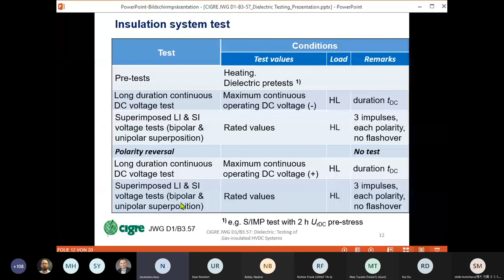calculated or can be evaluated by simulations or by real surface charge testing. After this, superimposed lightning and switching voltage tests are applied, both bipolar and unipolar superposition, and then the polarity is changed. The polarity reversal, or the test is done with the other polarity in the same way as mentioned before, and finalized by superimposed lightning and switching voltage tests.